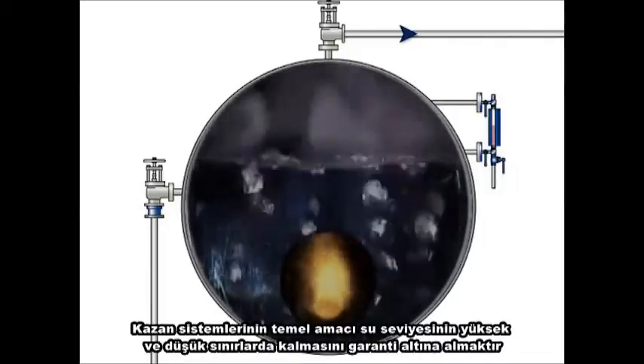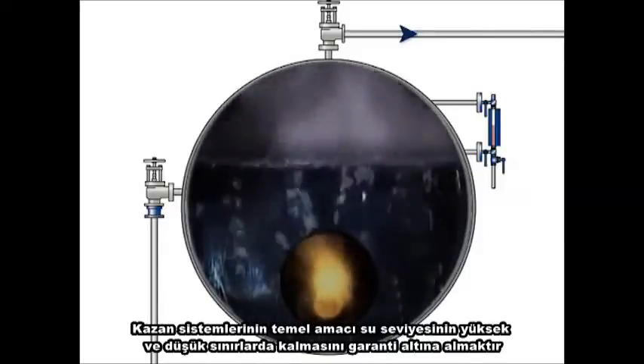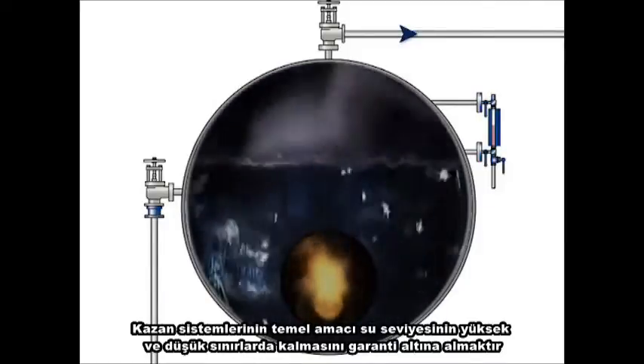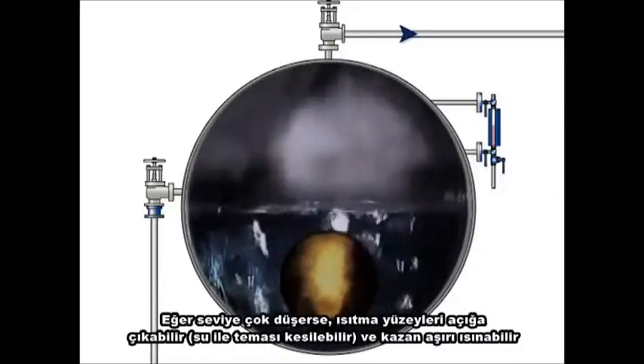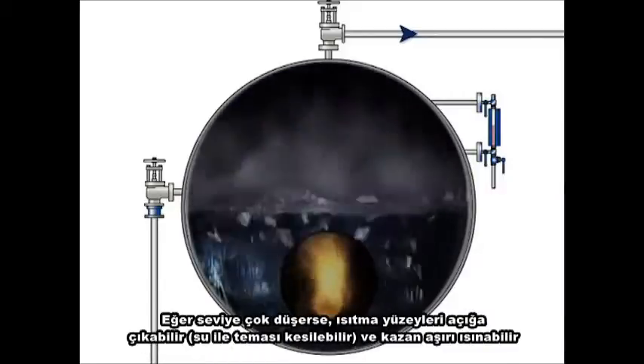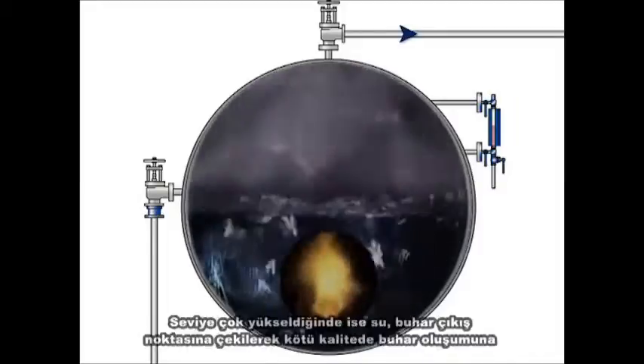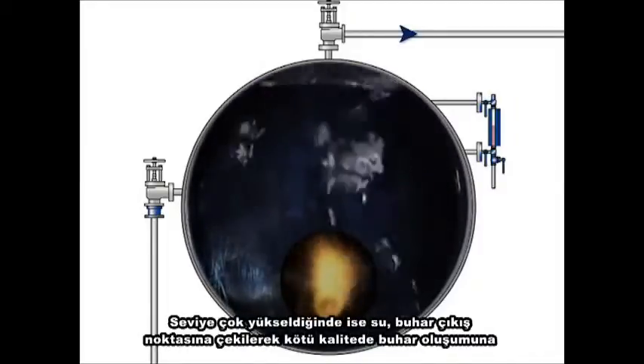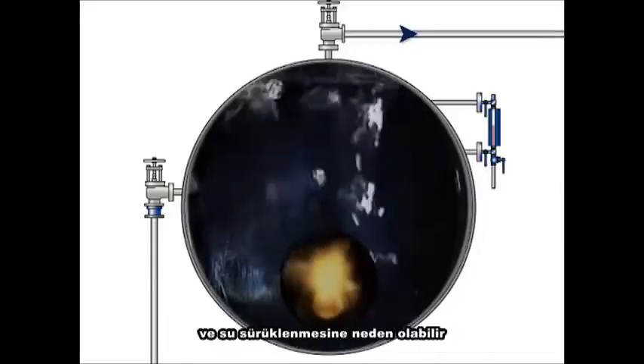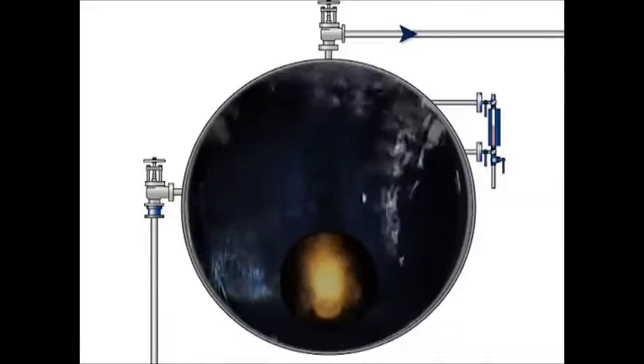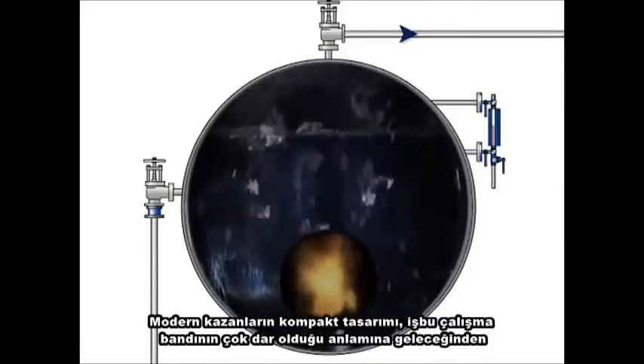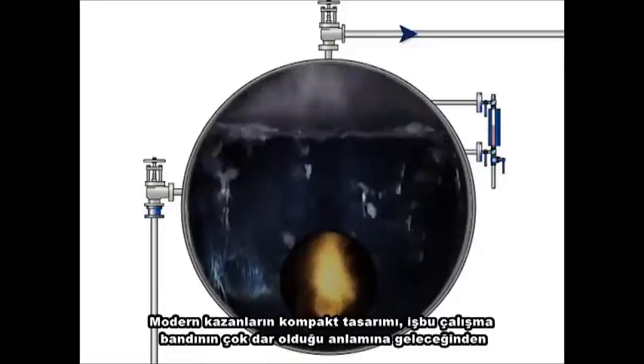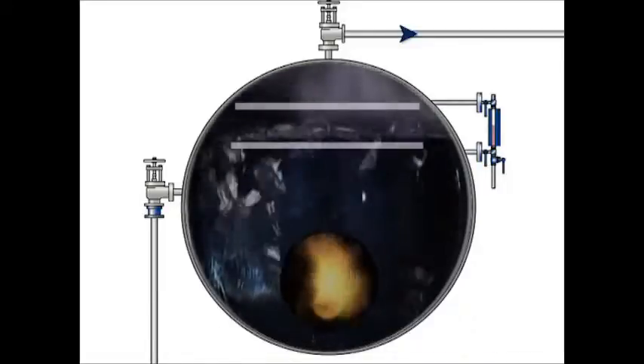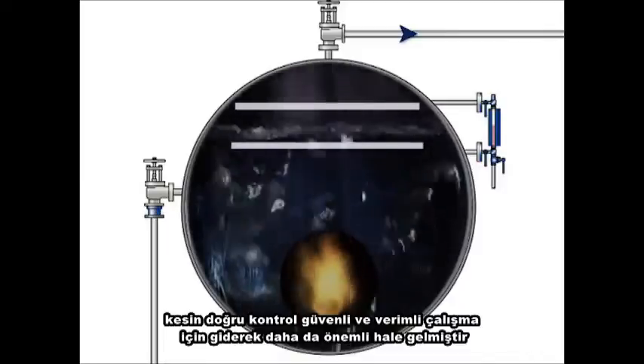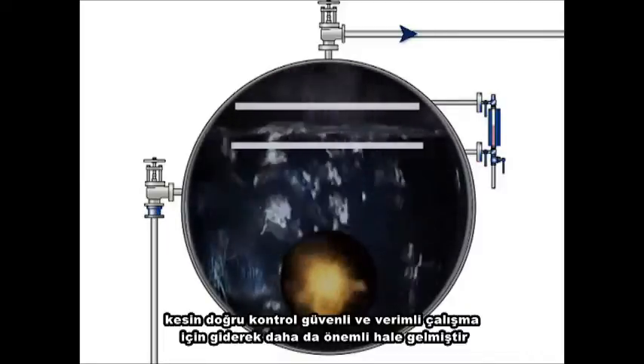The primary purpose of boiler control systems is to make sure that the water level stays between upper and lower limits. If it falls too low, the heating surfaces could become exposed and the boiler would overheat. Too high, and the water could be sucked into the steam takeoff point, leading to poor quality steam and carryover. The compact design of modern boilers means that this operating band is very narrow, so accurate control has become increasingly important for safe and efficient operation.